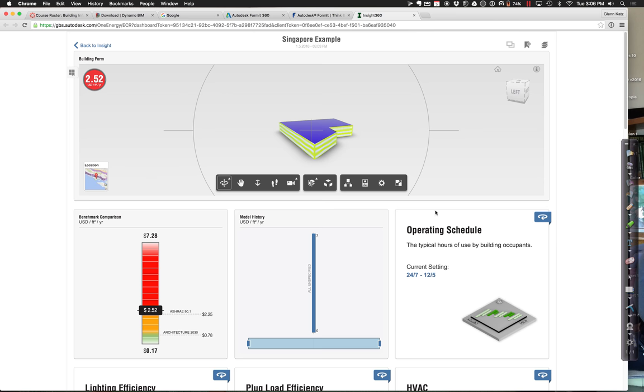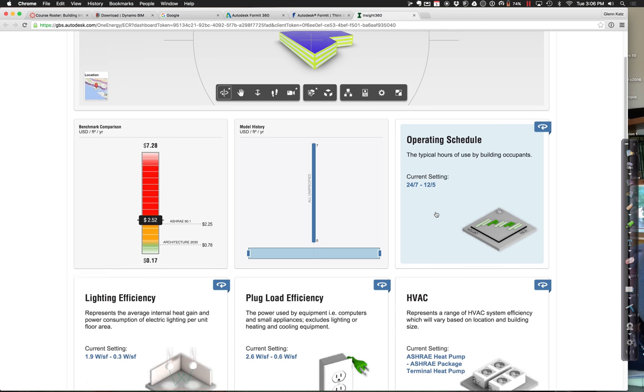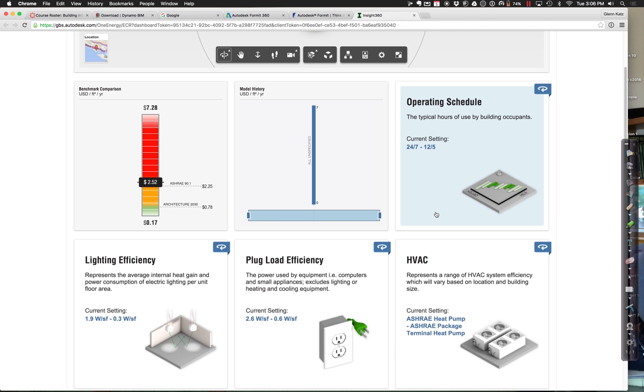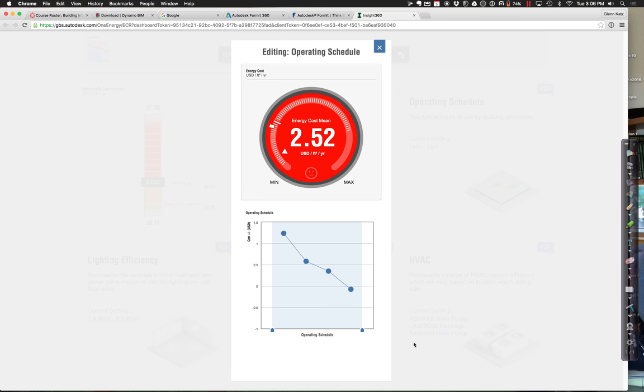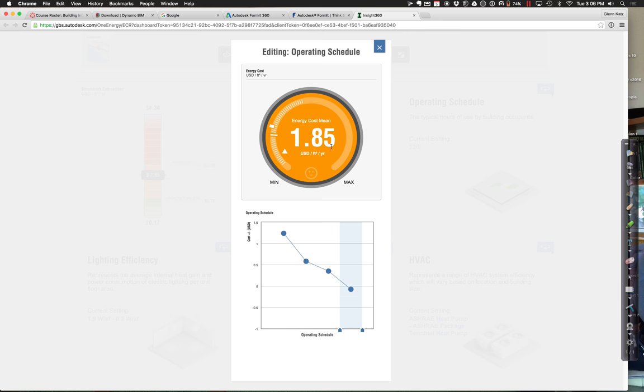There's this whole notion of really what the operating schedule of the building is. Right now it's set to 24/7, or anywhere from 24/7 to 12/5 hours. If we want to see the impact of tuning that up — going from 24/7 with an energy use of around 1.25, all the way down to 12/5, so five days a week, only 12 hours — that would lower it significantly.